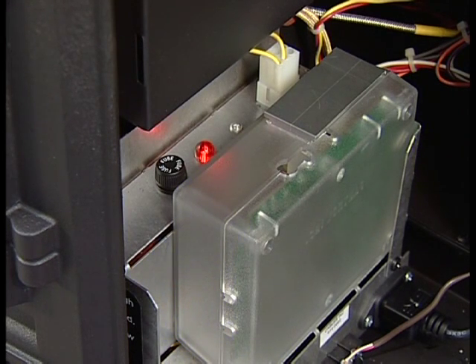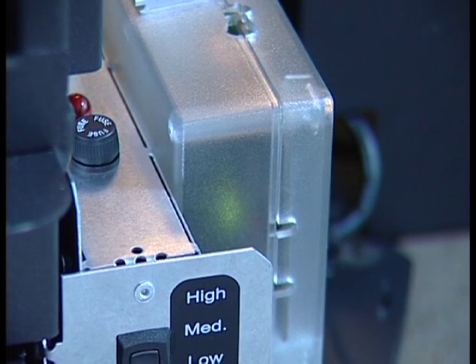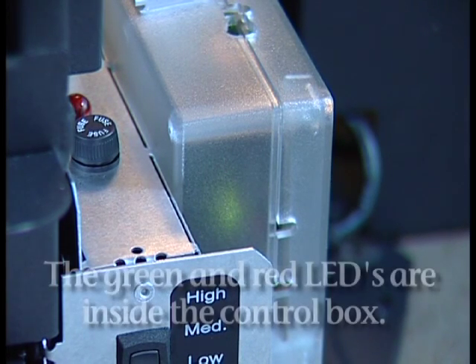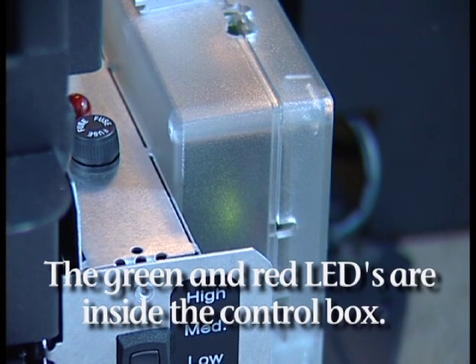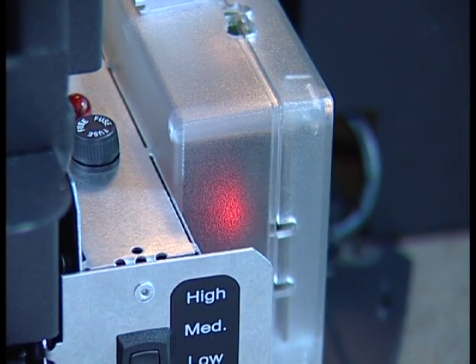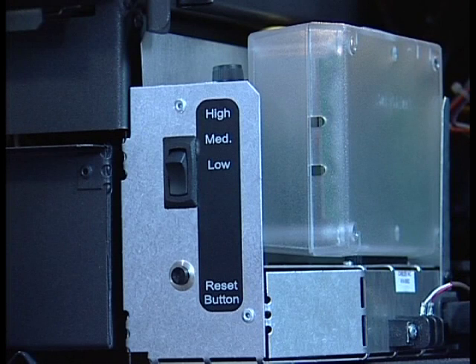Check the thermocouple lights on the control box. During the beginning stages of the combustion cycle, the thermocouple light will turn green. This will tell the control box to start feeding fuel to the firebox again. After the fire continues to get hotter, the red thermocouple light will turn on. This tells the control box that the fire has reached its normal burn temperature. If the lights on the control box do not come on, it could be a bad connection, thermocouple, or control box.